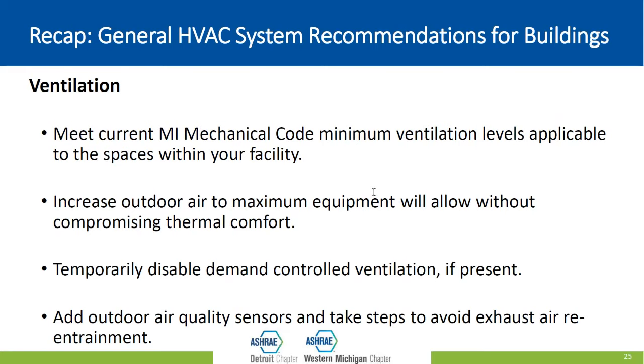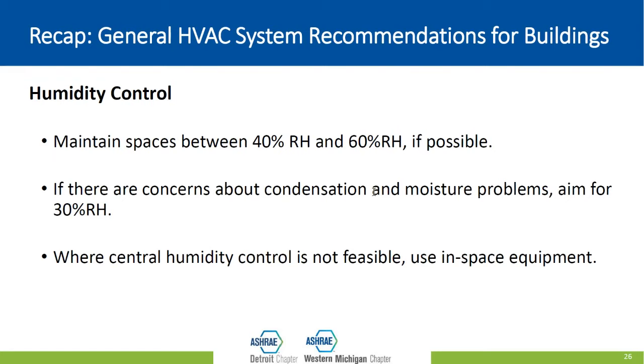Next slide. Humidity control, we want to make sure that we are maintaining our spaces between 40% and 60% relative humidity to the greatest extent possible. But of course, if we've got concerns about condensation, then we want to look at 30%. And that 40% to 60% ranges over the seasons, right? So in the summertime, you're going to be in that 50 to 60% range. In the wintertime, you're going to be in that 40 to 50% range, right?